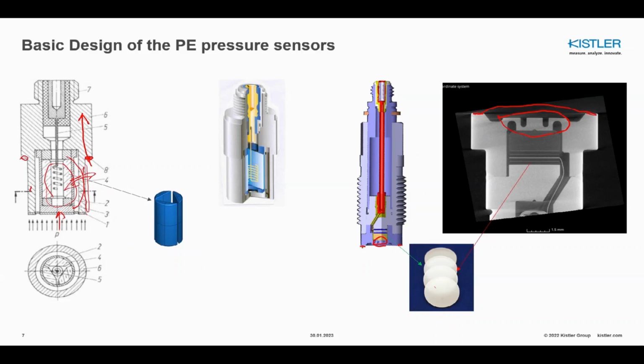The front sealed sensor, as I said, has a sealing surface here and here, and the membrane is here and it's acting like this. So the design of the sensor must be in such a way that the mounting force goes directly through the sealing surface to the nut and does not touch the membrane itself. So that's the reason why the shape of the membrane is so complicated, to allow all mounting forces to go directly to the nut and not touch the membrane.